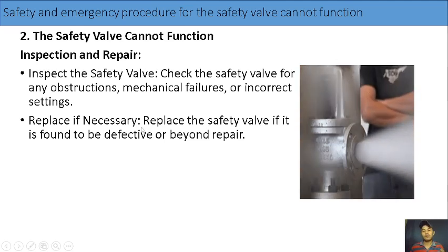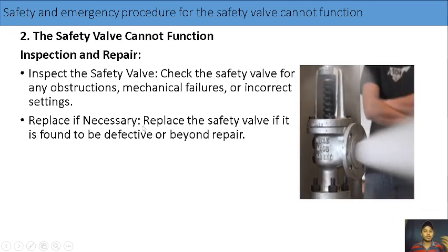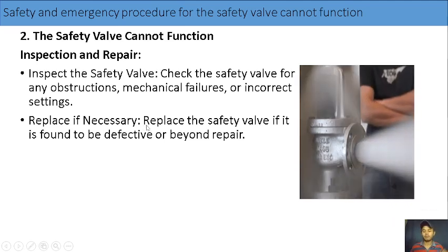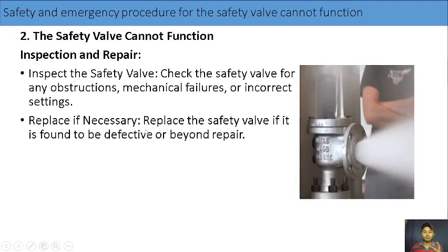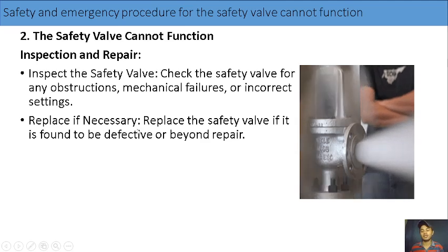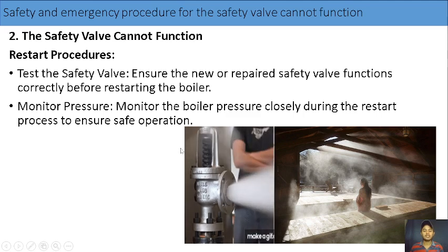So usually we have two safety valves. You have to check the one that is not working and replace it if possible, so that two safety valves will be working when you restart the boiler. Replace if necessary. If the safety valve is found to be defective or beyond repair, replace it immediately, or you rectify the problem. Next, if everything is now okay, you put back the working safety valve. You can now restart your boiler.